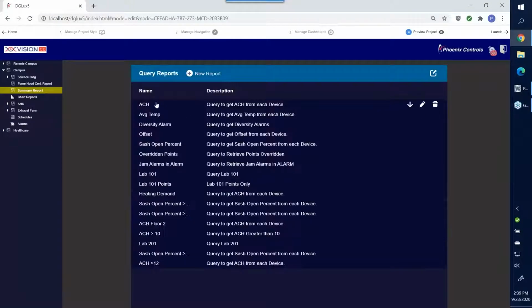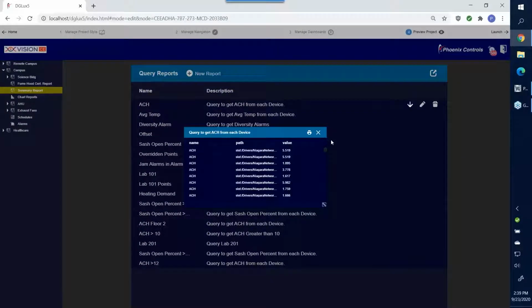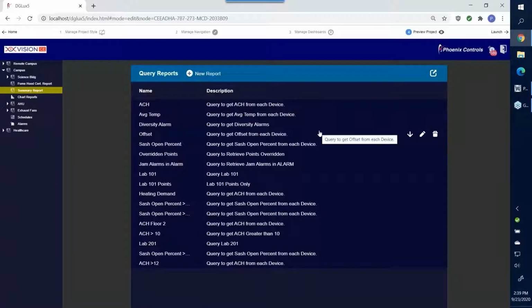In addition to these specific floor plans and requirements, there's a number of additional reports we can provide, from a summary of reports that gives you all kinds of individual criteria. When you run these, it looks at all the points associated with a particular area—it could be an operating room, could be a suite of operating rooms where you want to see the air change rates, or where you want to look at particle analysis. Again, there's really no limit. You can create your own criteria, like just show me the ones that have an ISO classification greater than 8 or greater than 7, which determines its cleanliness.